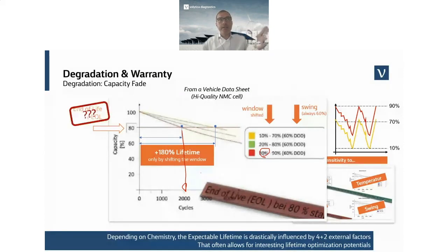Now, why did I say end of life? Does this thing look dead? No, it's happily living on. Don't confuse end of life with end of warranty. The warranty conditions end at 80%, but not the life. Batteries live longer than the warranty conditions. Every yogurt and every pizza lives longer than the best before date. Keep that in mind. There is a lot of value behind this wall.